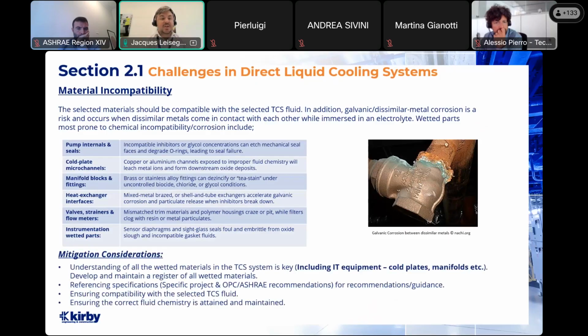So some mitigation considerations. What can we do to mitigate this risk? I think an understanding of all the wetted materials in that system is key. This includes the IT equipment. Often we don't always have that information of what that IT equipment is, what the cold plates are made from, what the manifolds are made from. So this is a key part in understanding what those materials are and developing and maintaining a register of all wetted materials.